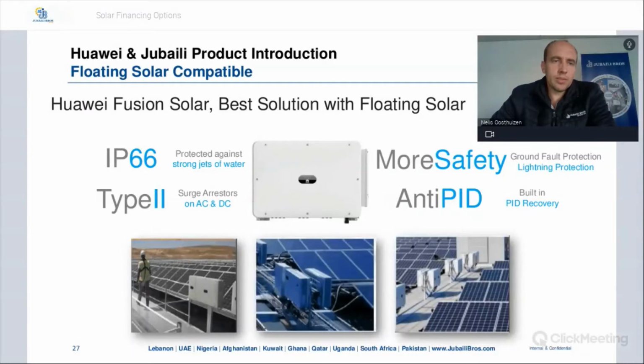Next slide, Huawei inverters are compatible in floating solar situations. The inverter itself is rated IP66, which means it is protected against strong jets of water. It has built-in surge protection type 2 on both AC and DC. It has anti-PID features safely built in. So all of this assists you on a floating solar PV plant.